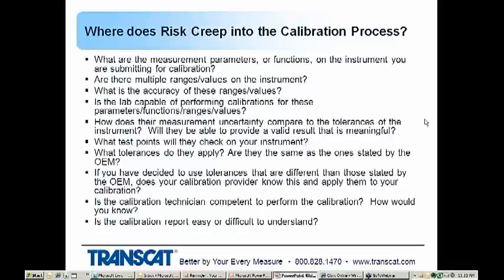If those tolerances are tighter, you're being told to perform a nonconformance review when you probably don't need to, and you're wasting resources. So it's very important that you ensure that those tolerances are correct, not just looking for out-of-tolerance conditions, but especially initially when sending an instrument to a calibration provider. First time you get that back, check those tolerance limits, make sure it's what you expected it to be.